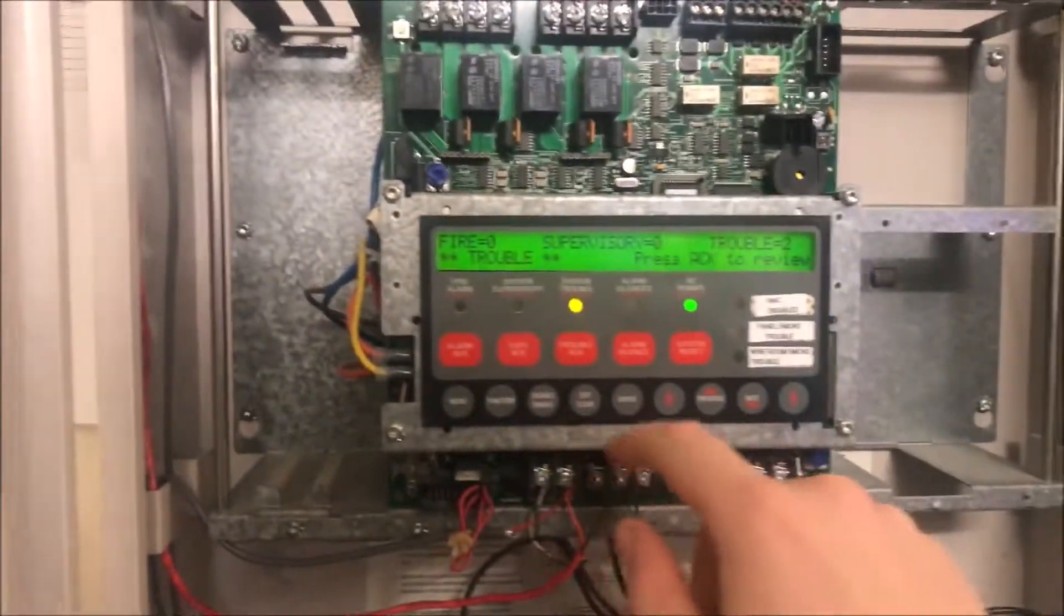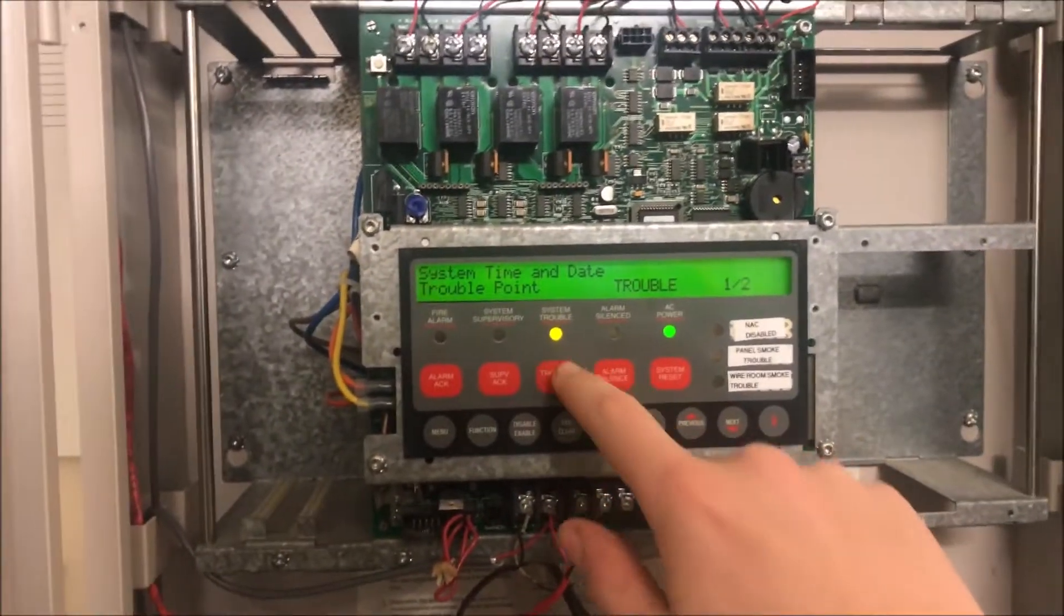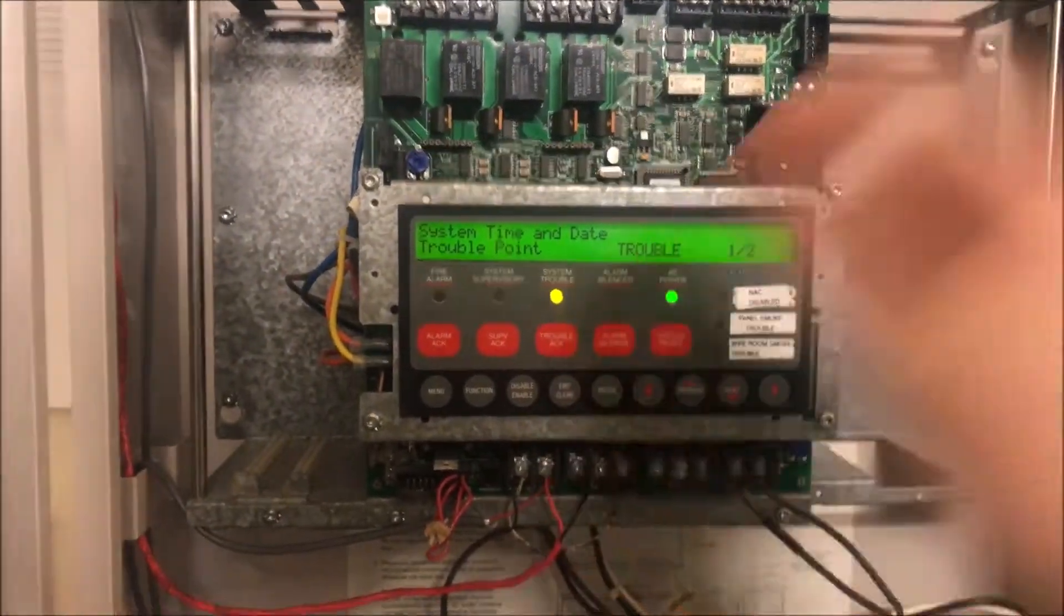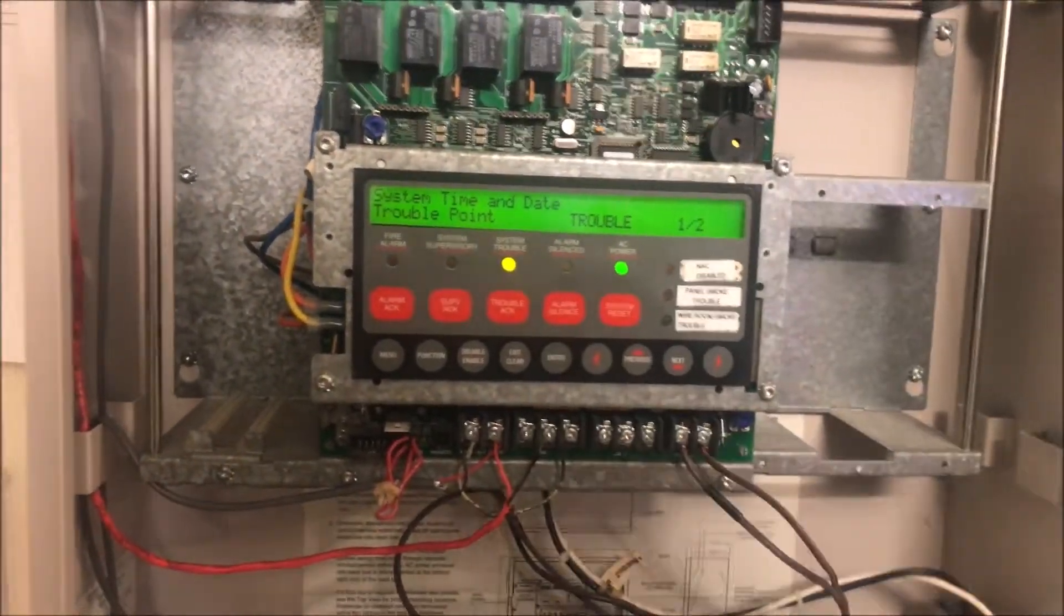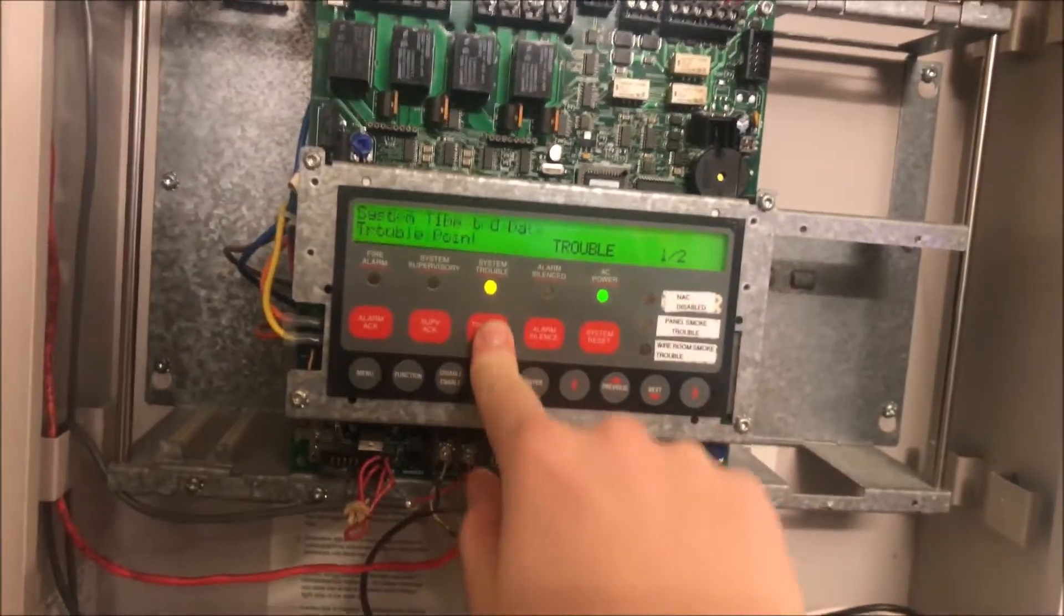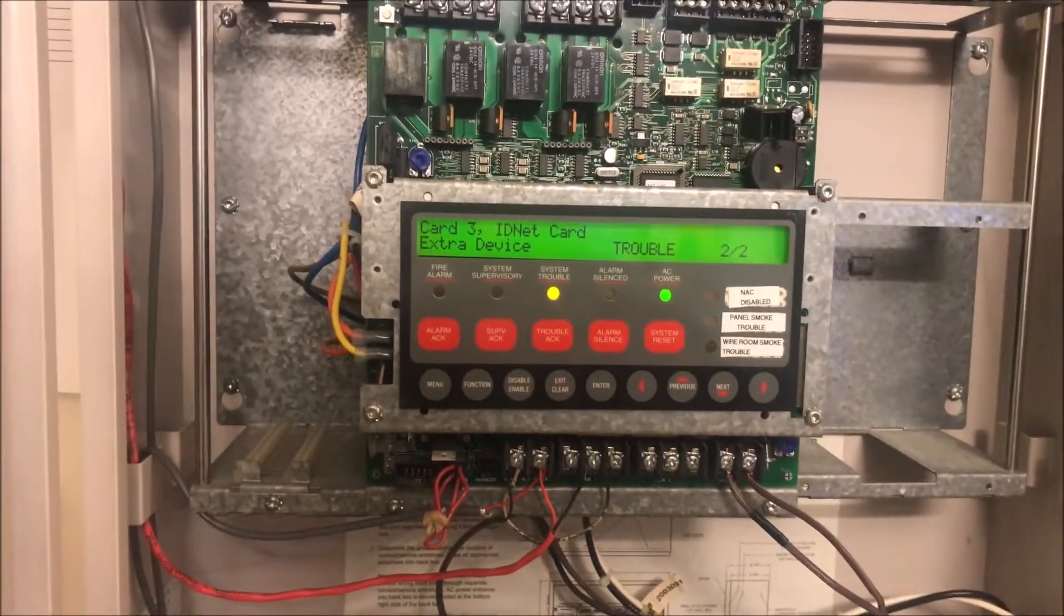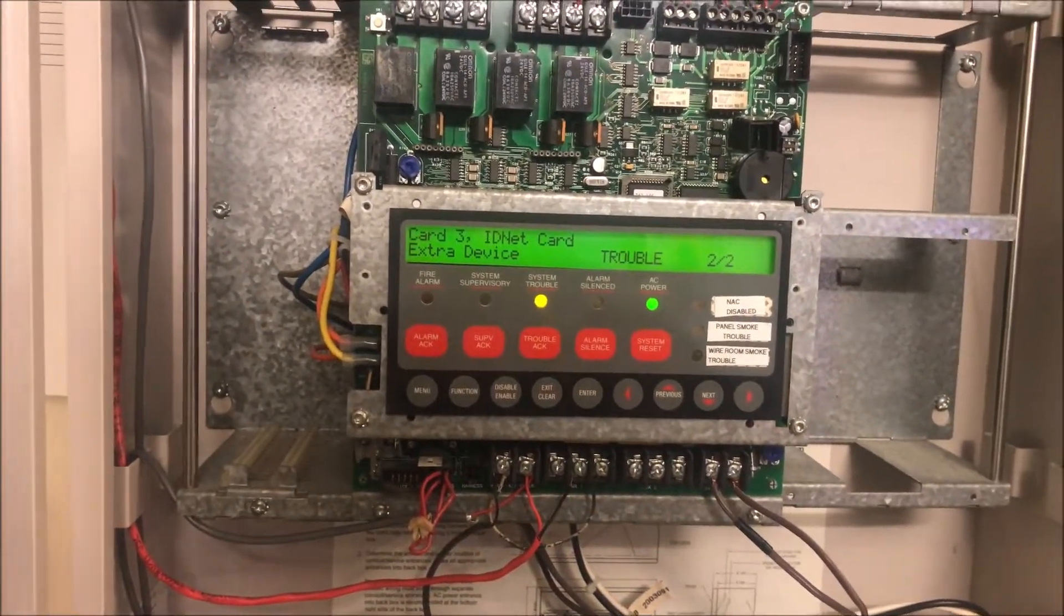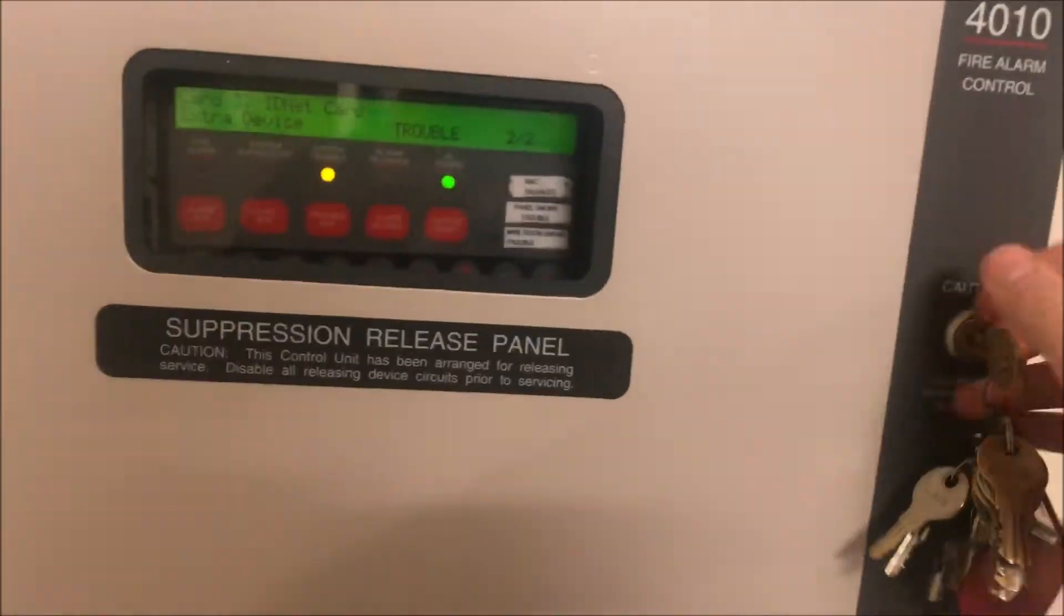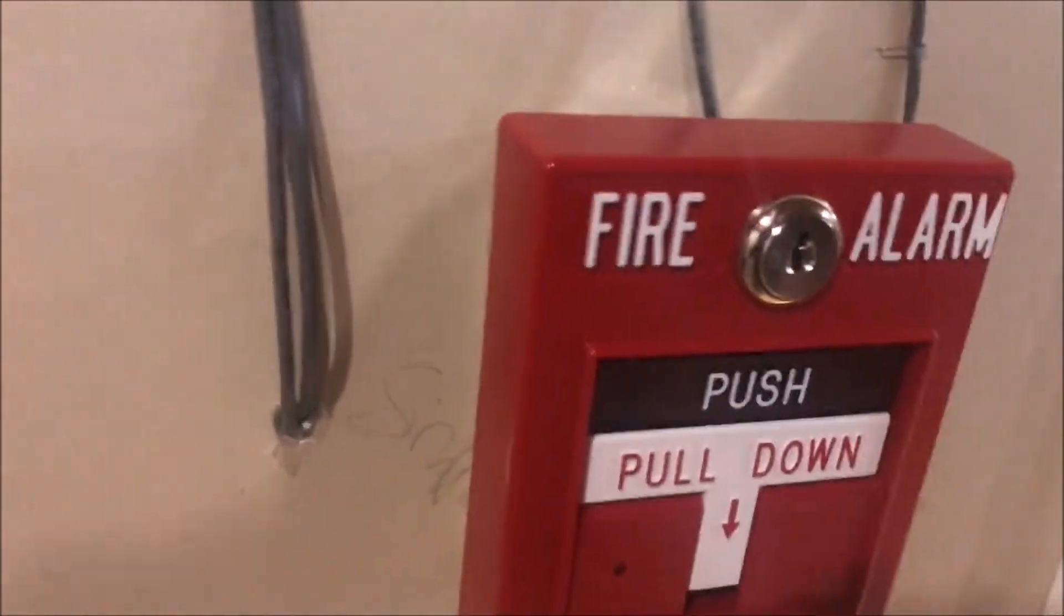So first off, we have two troubles. One is because I just restarted the panel, so it has a time and date trouble. And then two is because of an extra device trouble. That extra device trouble is in here - this is the pull station.